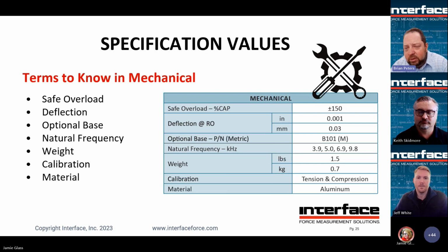But that's good to note too if you start getting into dynamic or high cycle testing, to keep in mind in terms of how stiff the sensor is. And then weight, calibration. Not all sensors get the same calibration, so you'll want to note, do you have a tension or compression? You can typically use sensors in opposite modes. They should be pretty symmetric, but again, if you want to have that specific mode cal data, you can always ask for it if it isn't standard for that model. And then material.